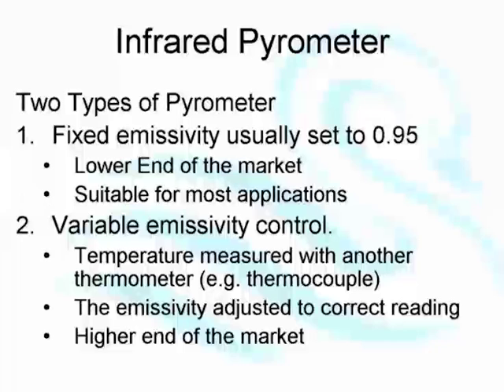There's two types of infrared temperature sensor. There's the type that have a fixed emissivity, and it's usually set to 0.95. They're the cheap ones. Now, when you're measuring temperature with a cheap infrared temperature sensor with a fixed emissivity, you're not actually measuring temperature. What you're actually measuring is the color of the object. You're actually measuring whether it has a matte or a shiny, gloss surface, because matte surfaces are better at absorbing and emitting infrared. So you're just measuring the color of the object. The more expensive infrared temperature sensors, you can vary the emissivity, and they will give you a correct temperature reading.